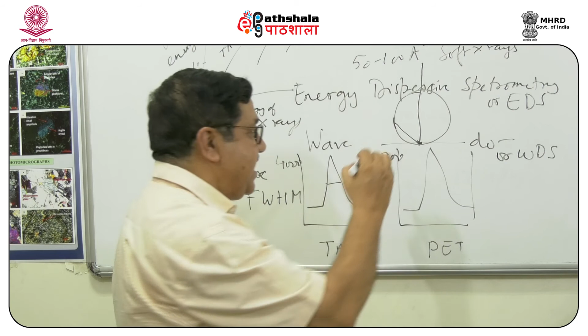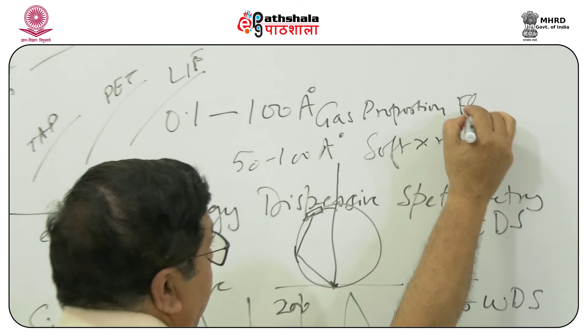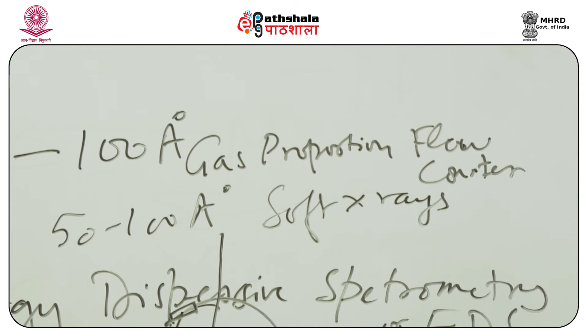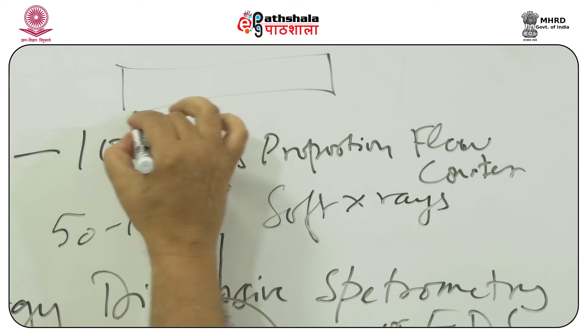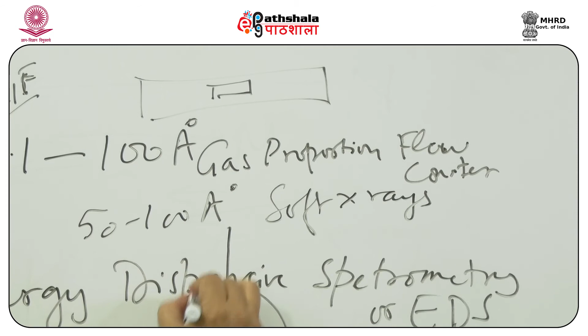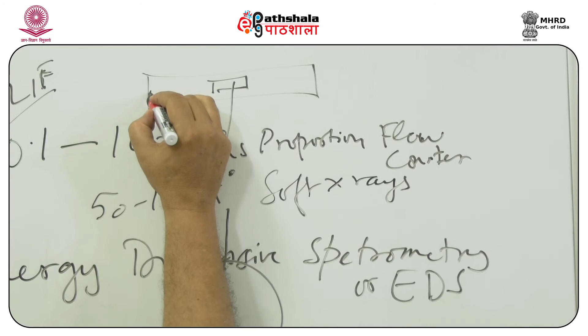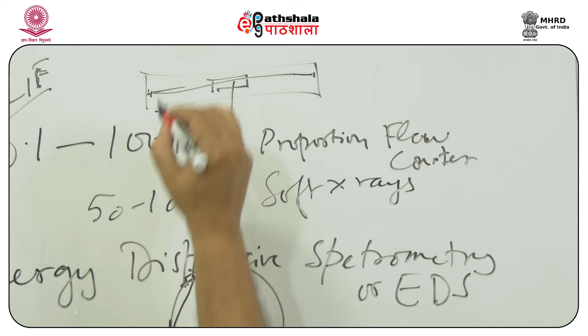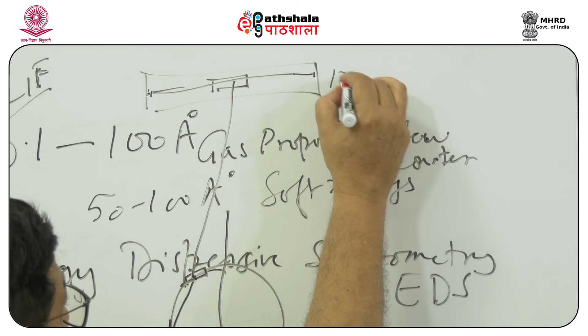There are two kinds of detector. The common detector is known as the gas proportional flow counter, which is a tube-like device, like this, with a window where these X-rays are directed. Then there is a center wire, which is provided with a positive bias or voltage, generally of the order of 1200 to 1800 volts.